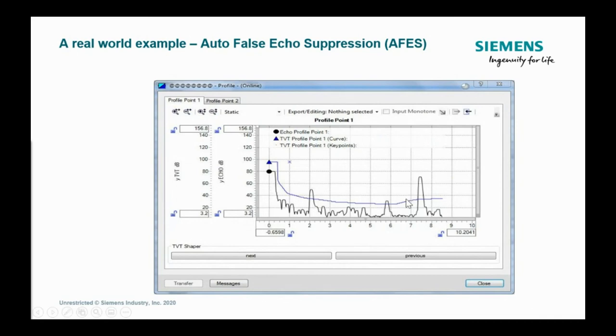Step number one, enter a distance. Step number two is we're going to tell the instrument to learn to that distance. Learn where all of these noise obstructions are. Learn where those bell end couplings are. And then step number three is we're going to go in and enable, or tell it what to use, what you learned. Some instruments in the portfolio will automatically do step number three. I always say, if you go and enable something that's already enabled, it stays enabled. That way I don't have to remember which instruments you have to enable, which ones you don't.